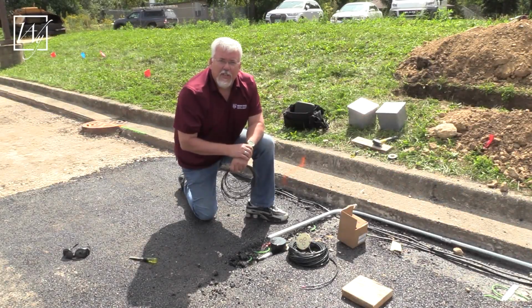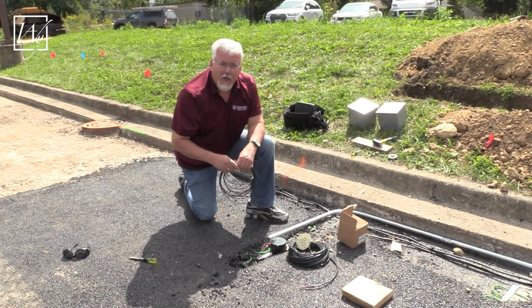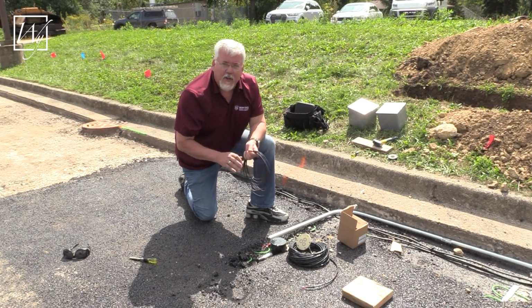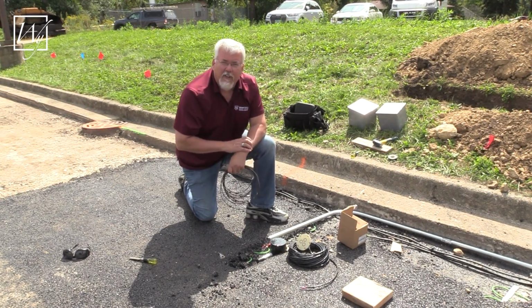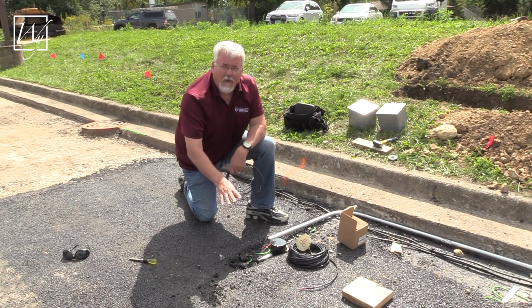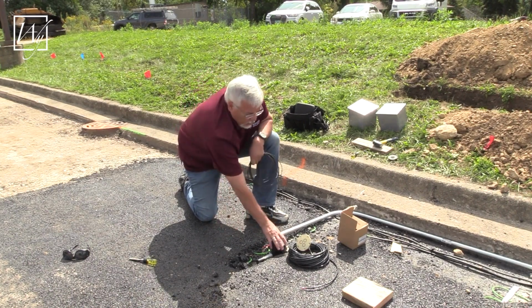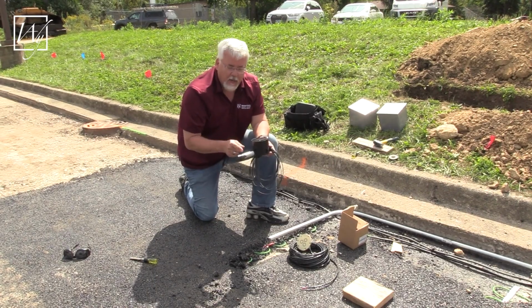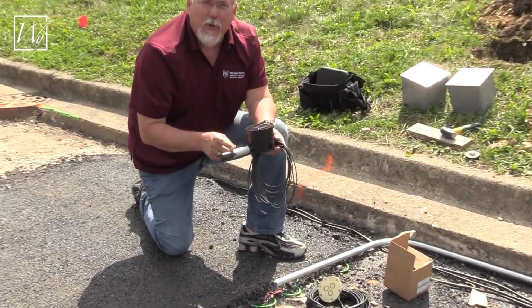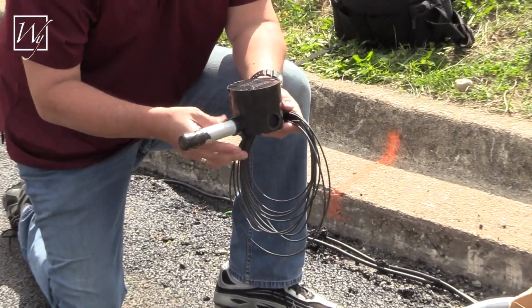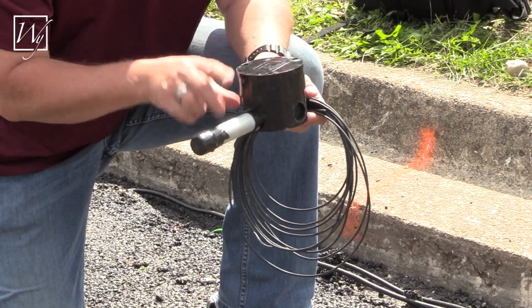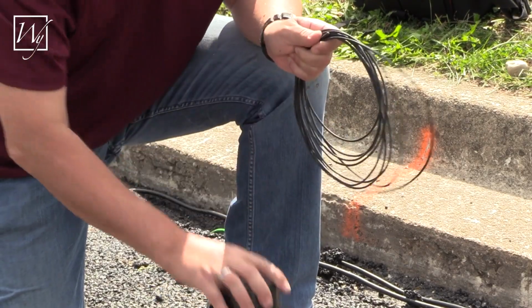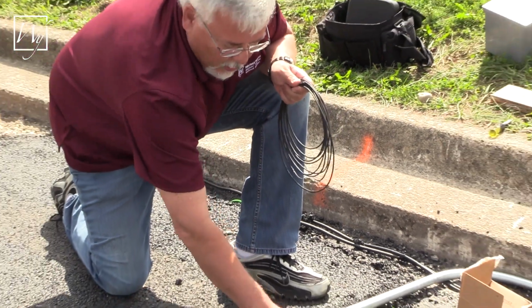There are actually two sensors in this particular installation. One is an over temperature sensor, which senses the temperature of the slab or the asphalt pad. It goes into this assembly and into a capped end of a rigid metal conduit, and it will rest right here, between two of the heating wires.